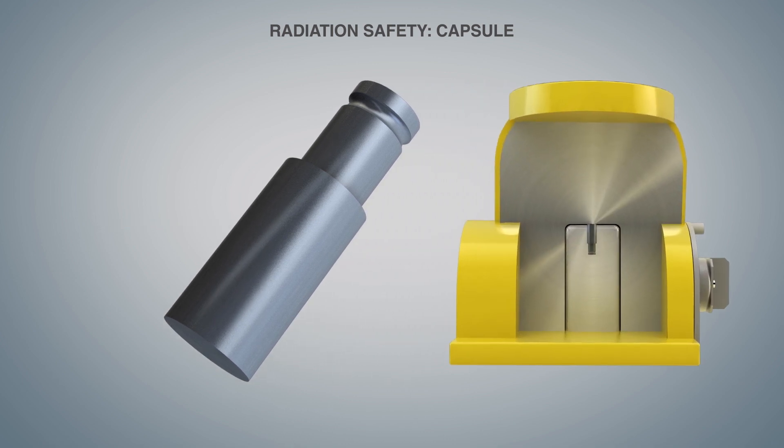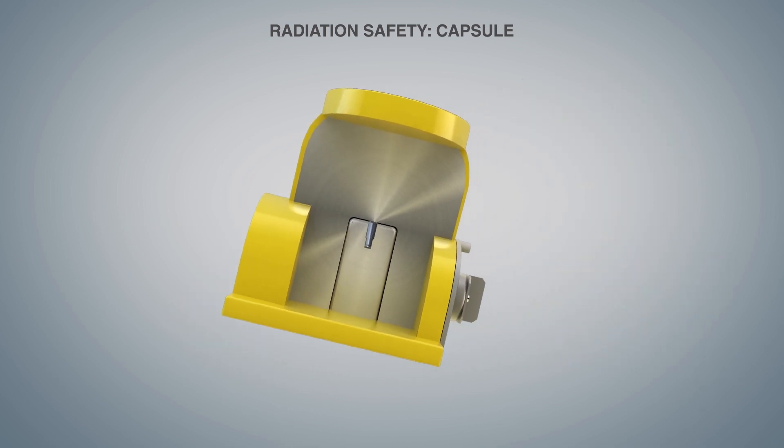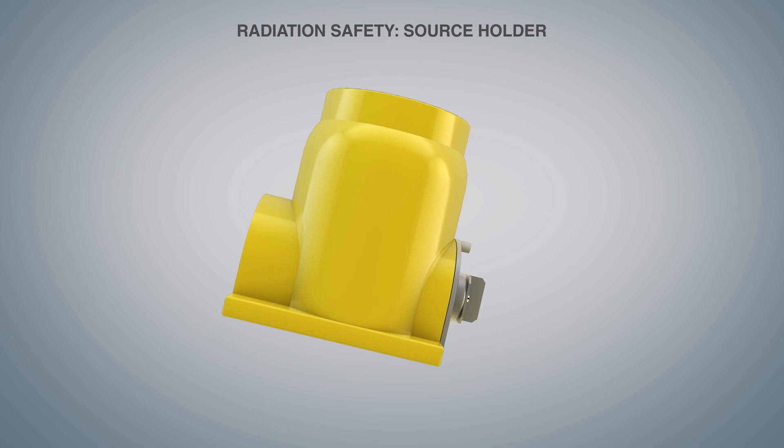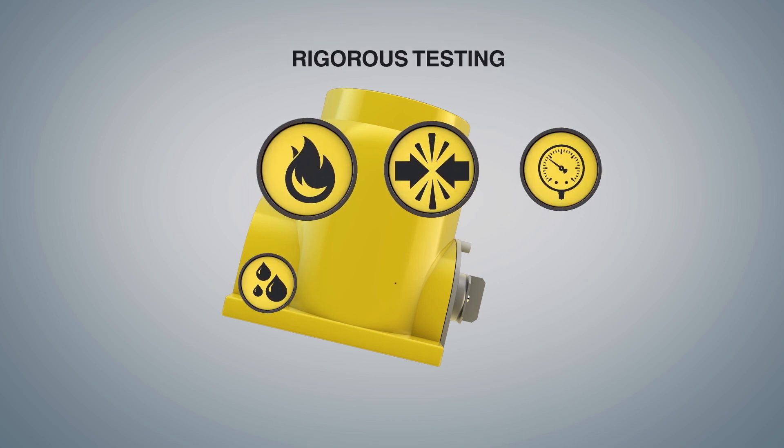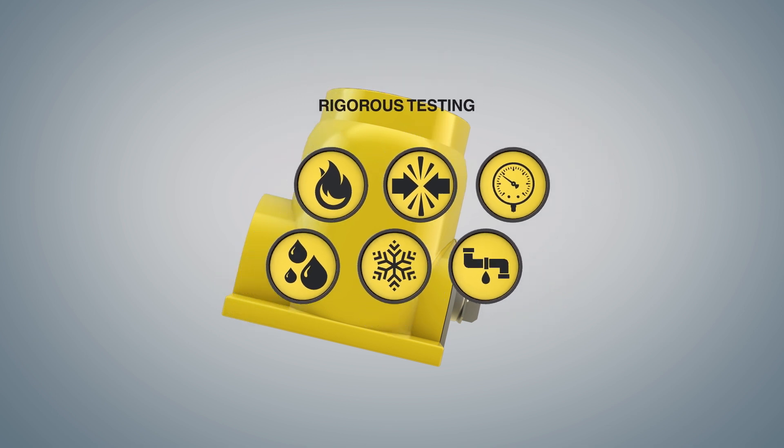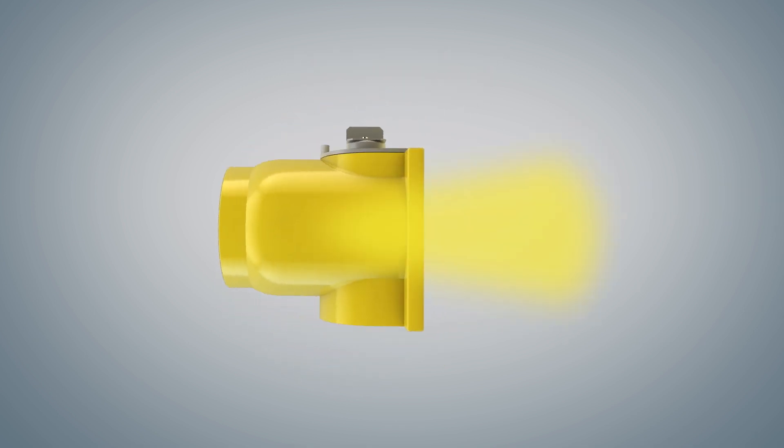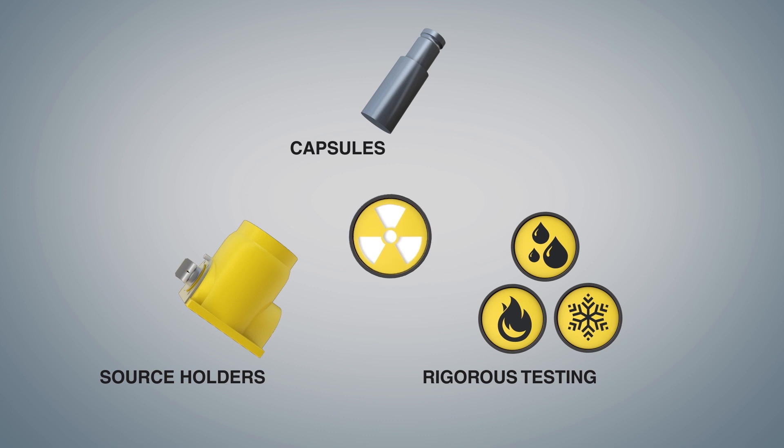But the chances of accidental contact are zero because each nuclear source is housed in a protective source holder. A source holder is a steel or lead-lined encasement that shields the outside environment from radiation. Source holders are rigorously tested to ensure they survive extreme conditions, and they are designed so radiation travels only from a guided channel called a collimator. These combined safety measures severely limit exposure to radiation.